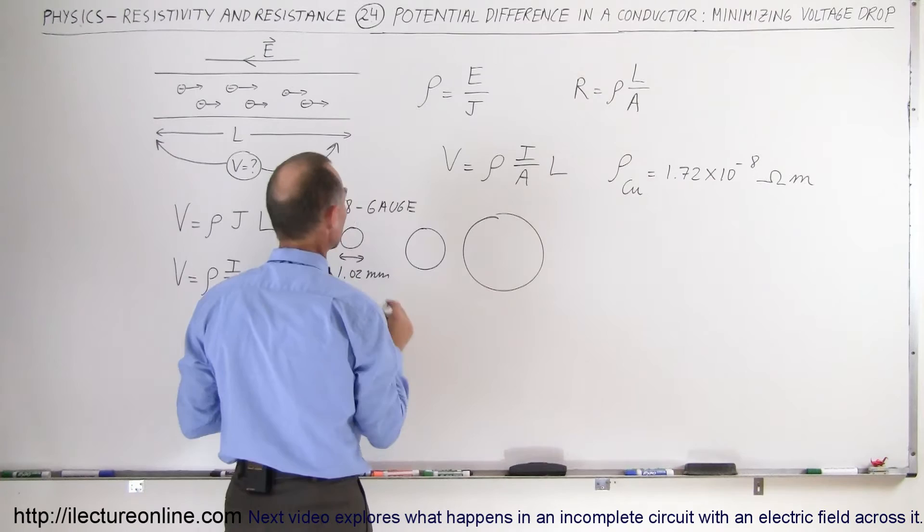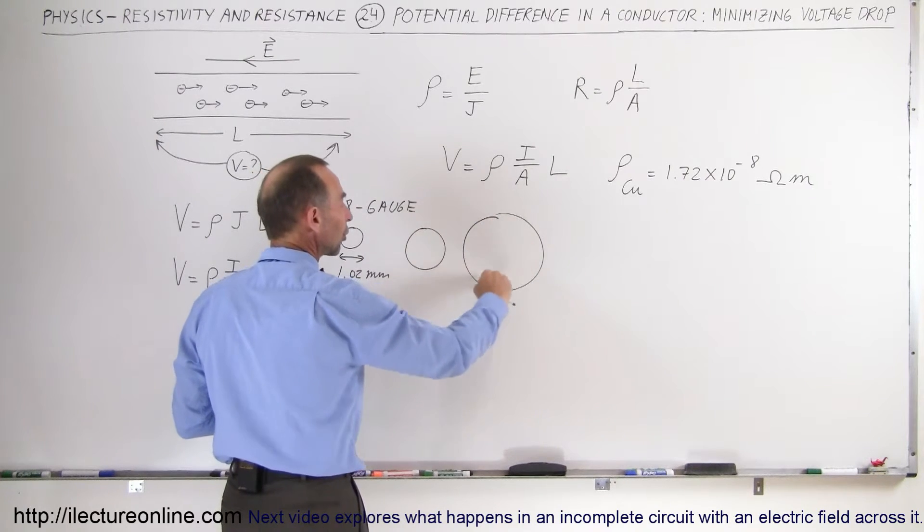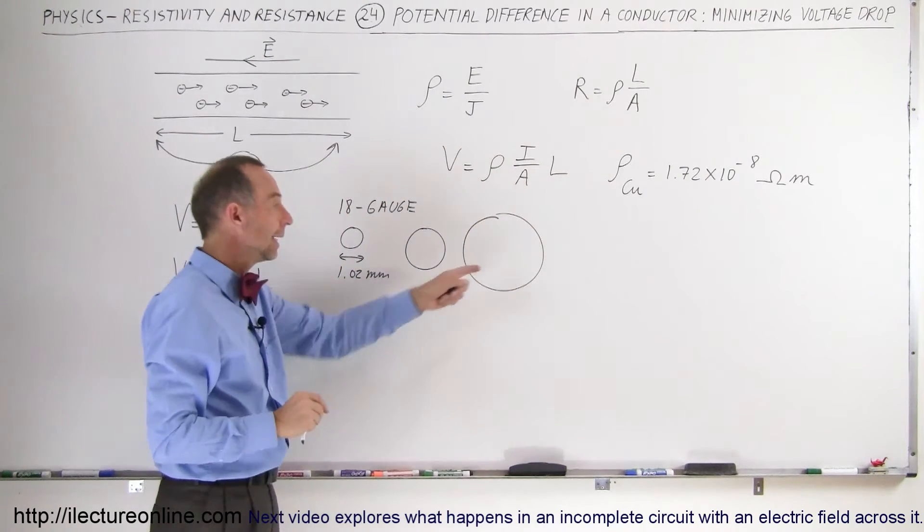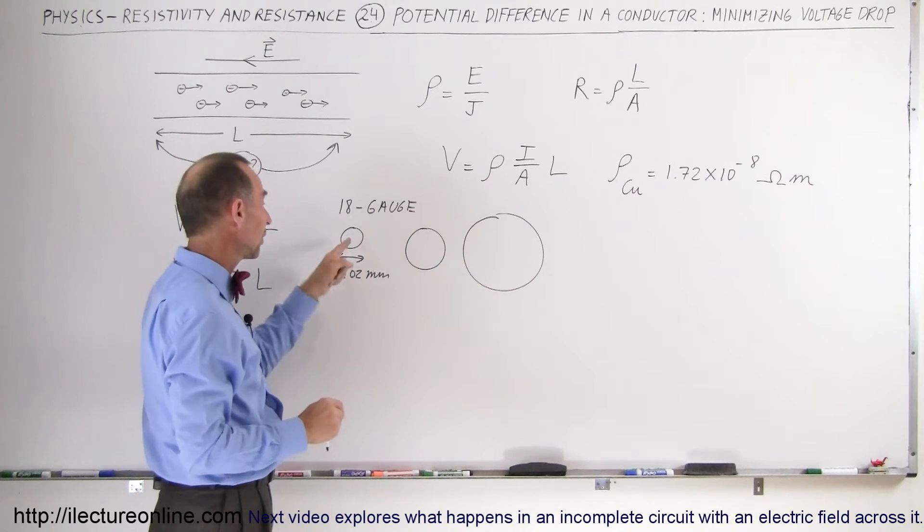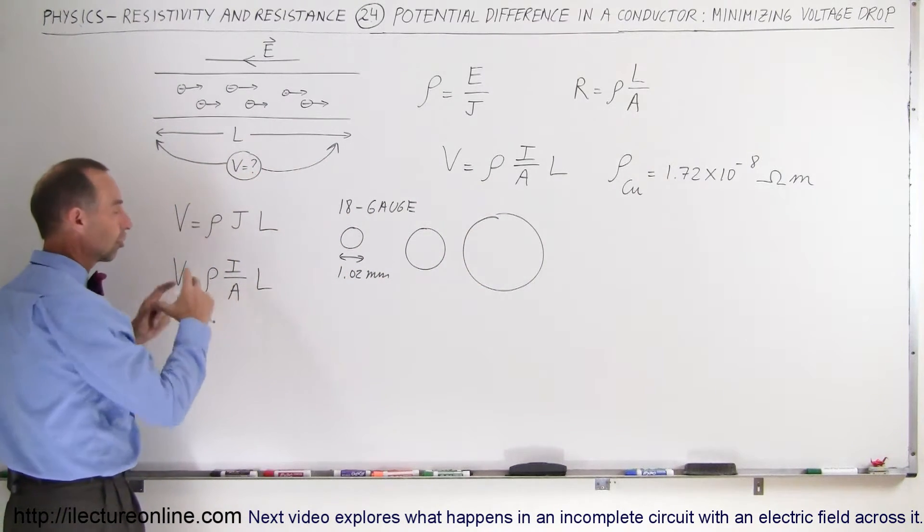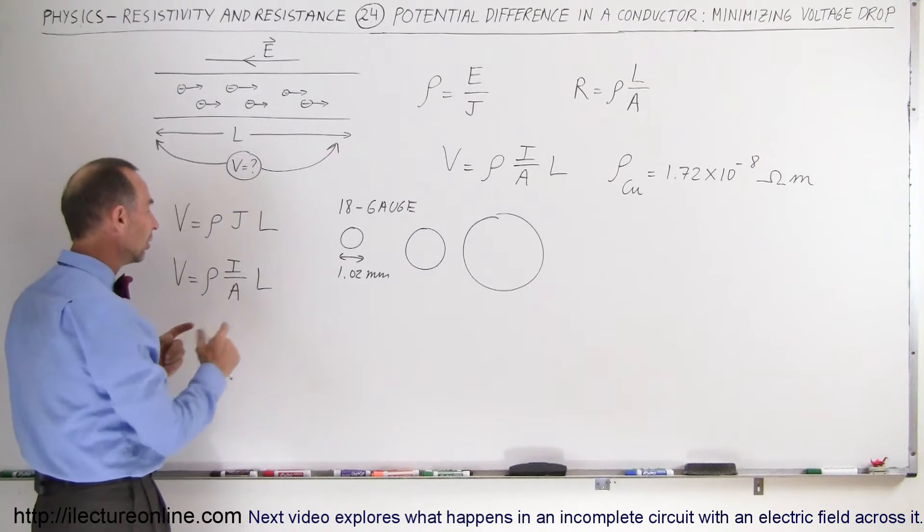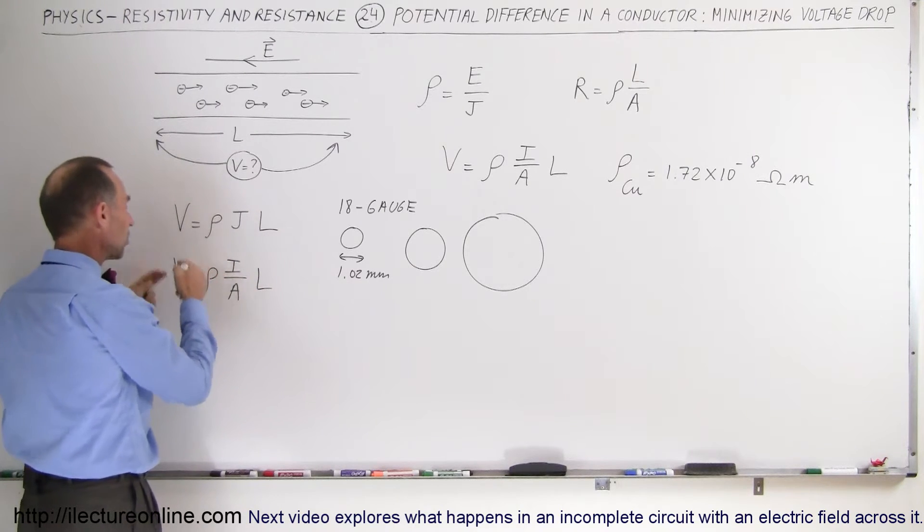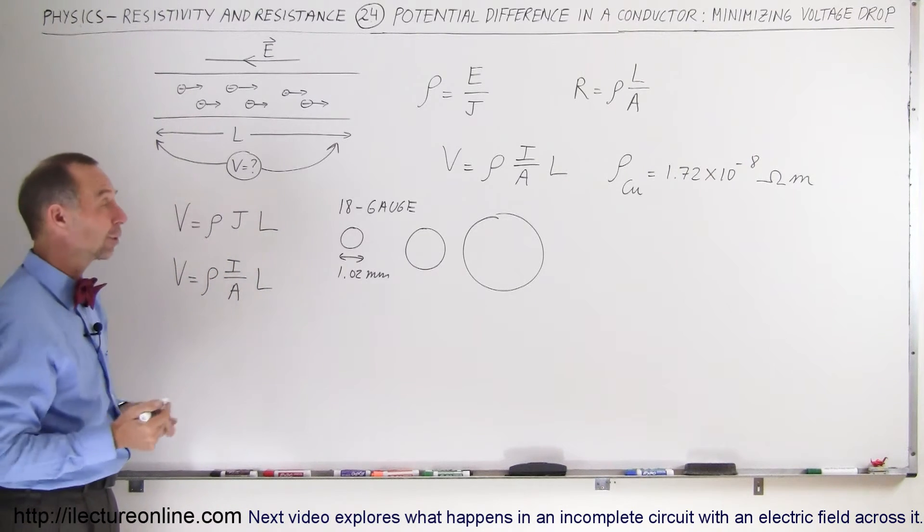You can carry a whole lot more current per unit area in a big conductor like this compared to a conductor like that. So the idea is to make the conductor as large as possible in cross-sectional area, so with the same amount of current, we have a much lower voltage drop. That's the only control that we have.